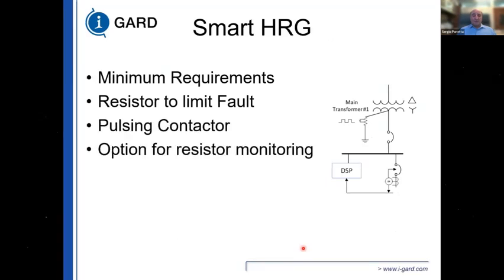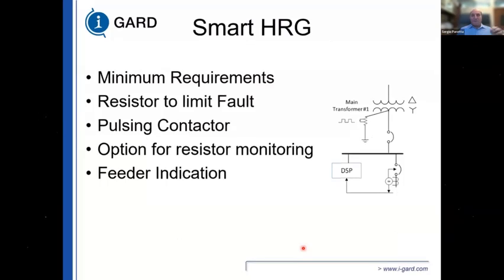The smart HRG system, now the minimum requirements is a resistor to limit the fault current, a pulsing contactor, option for resistor monitoring, because one thing we have in Canada is you have to monitor the integrity of the resistor ground path. If that resistor fails short-circuited, or if the path from the neutral point to ground has a ground fault in it, you're going to have a solidly grounded system. If it fails open, you have an ungrounded system.